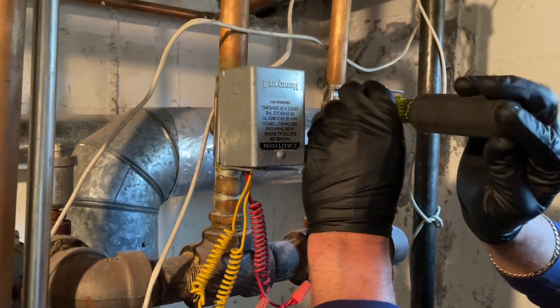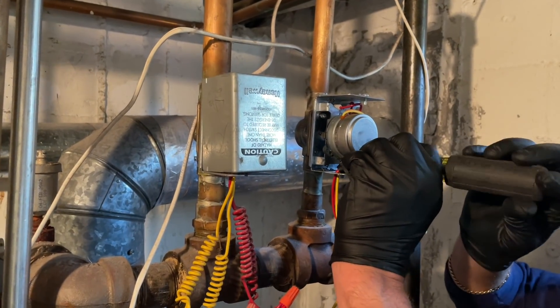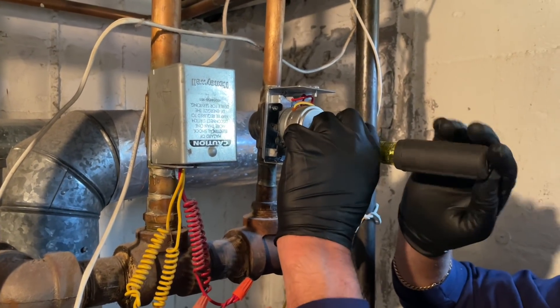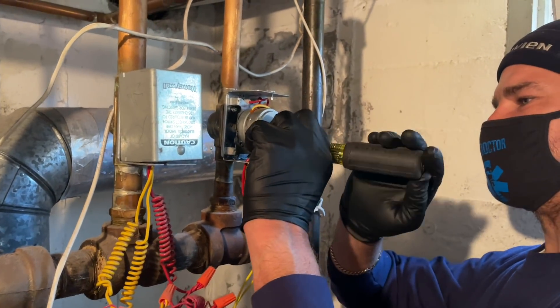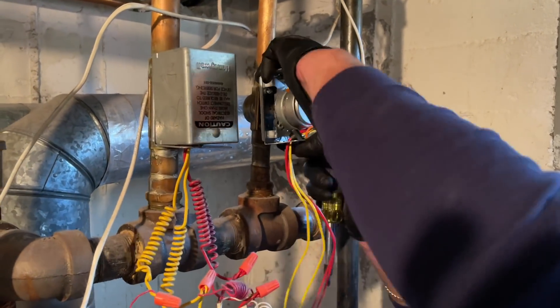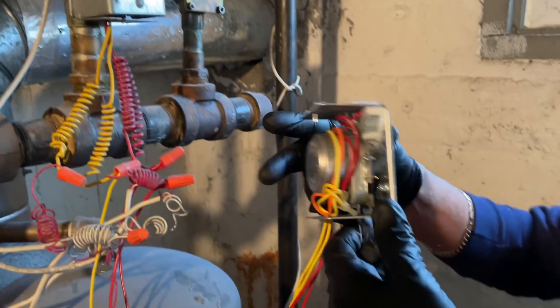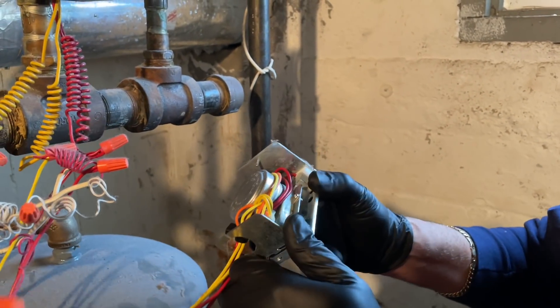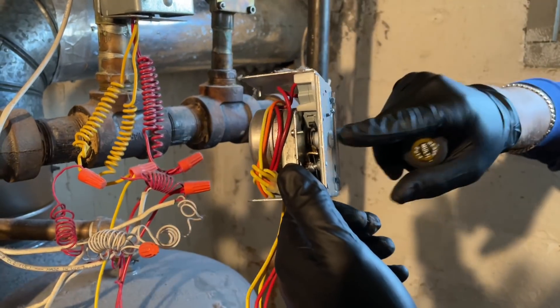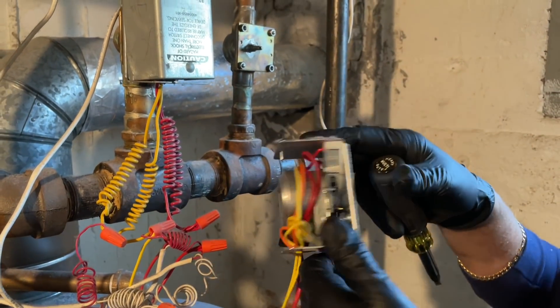So we're going to unscrew this one. See? And now the other side. I can go over the end switch wiring and all other good stuff. We use our friendly Wagos. There you go. See that? And now she's stuck, she's dead completely. As soon as I dislodged her from the actuator to the arm that opens that ball and moves that around. She's shot. Seized. The lever is bending. And she's ticking away.